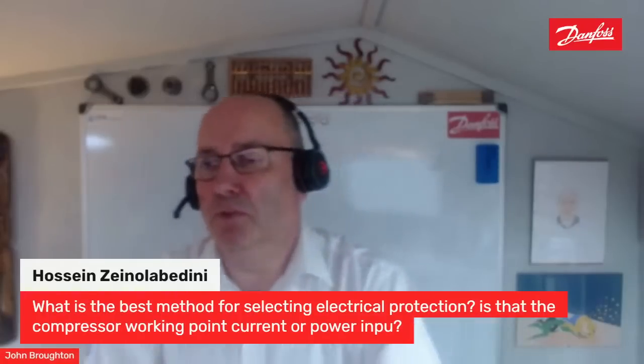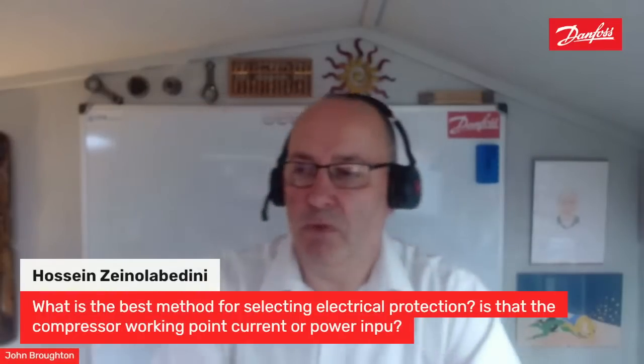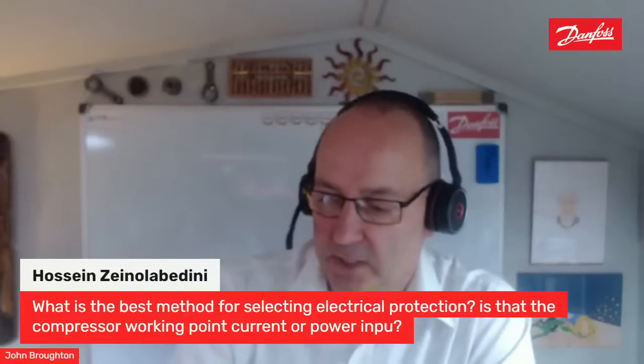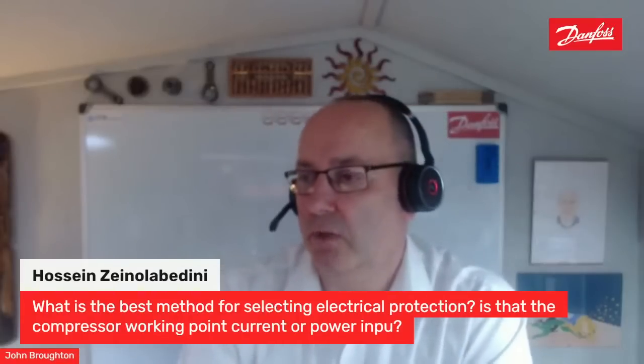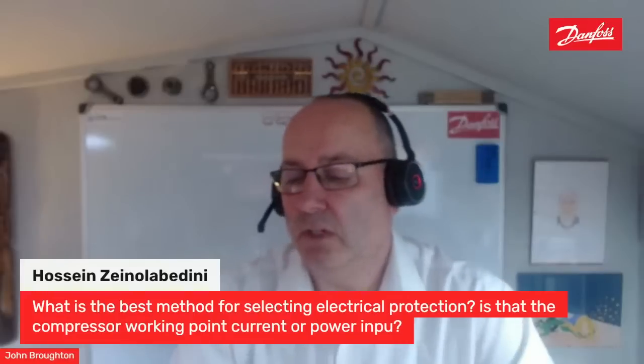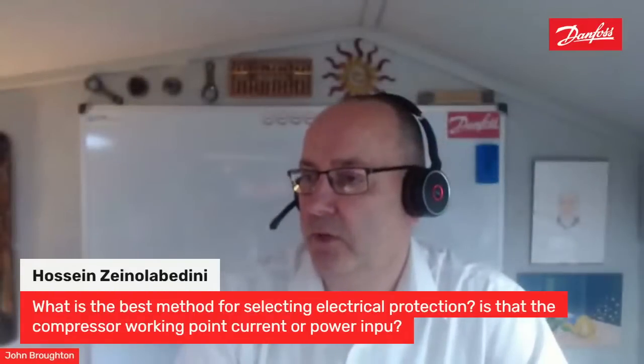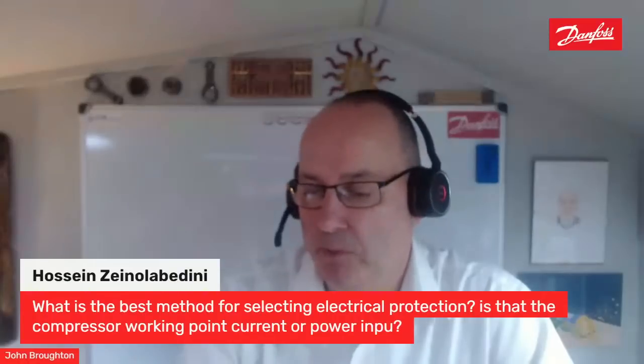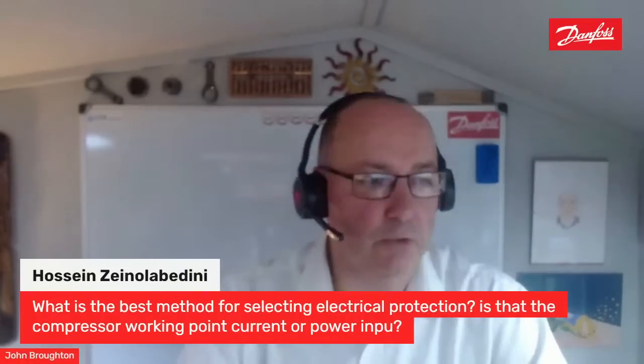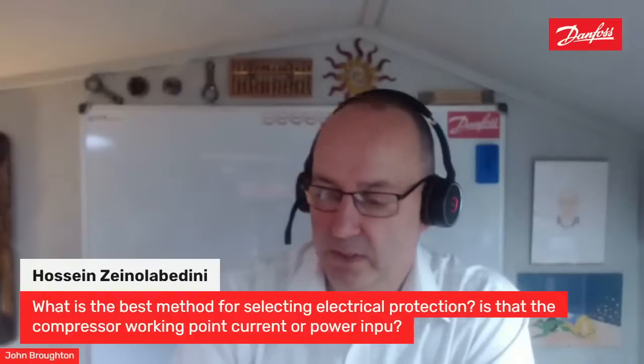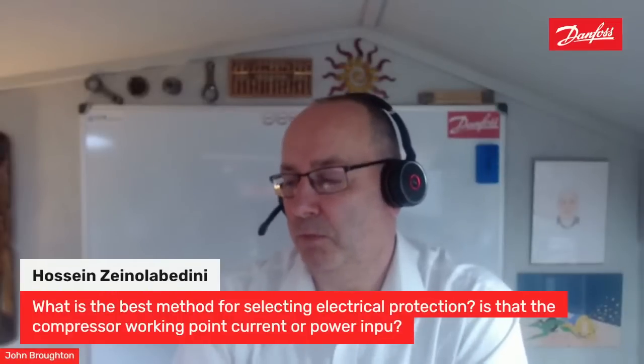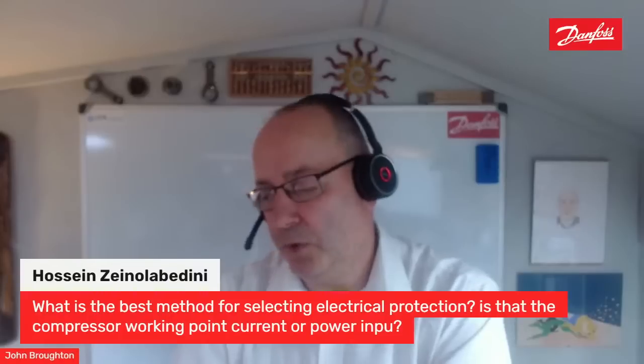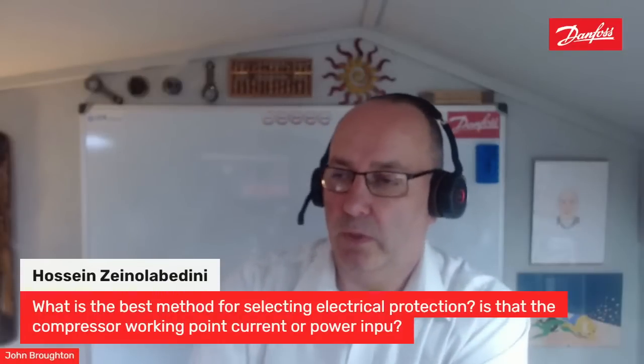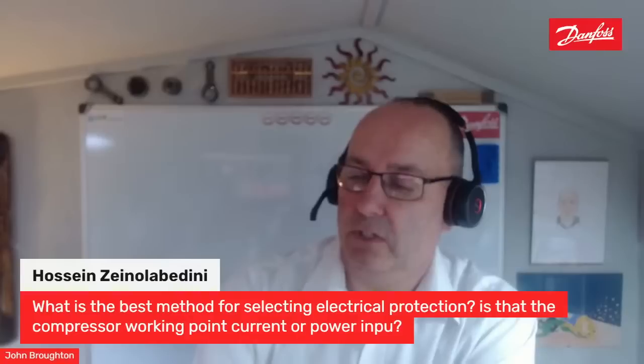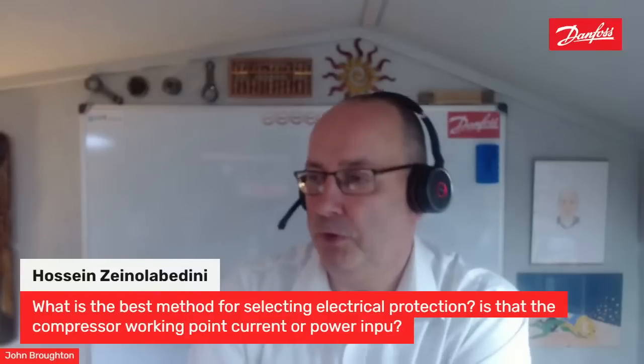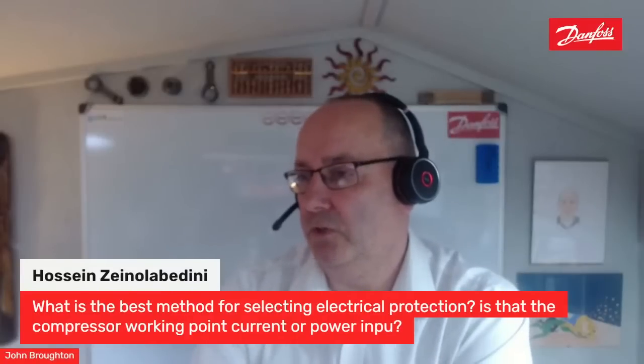I can't really say much else than that. It is important to make sure that your overloads are set, not right on the button, but close enough to actually give you some protection if that machine starts to pull higher amperage. And it's particularly important for cold rooms. We do have customers who use and abuse the cold room so that they will put more product in than they said they would. The product will come in at a higher temperature than they said it would. If they put, let's say, warm product in a cold room, then that compressor might not be able to cope with that.